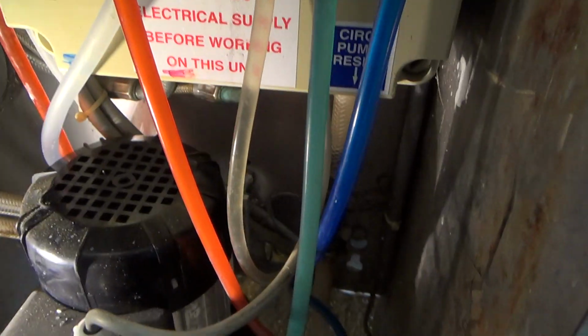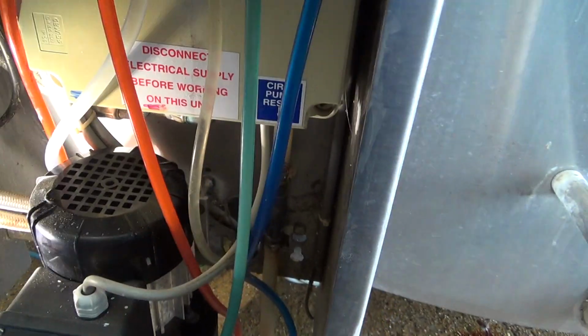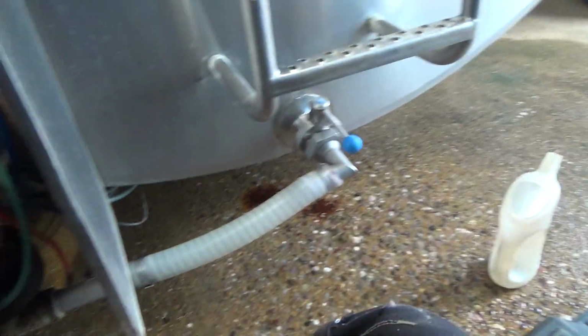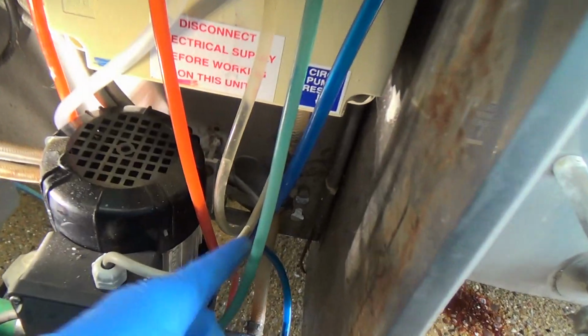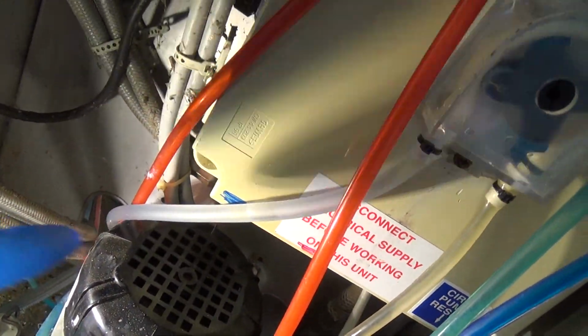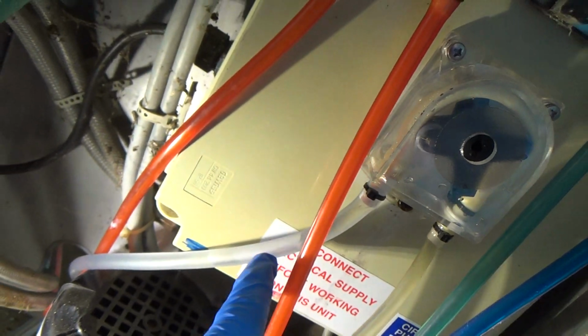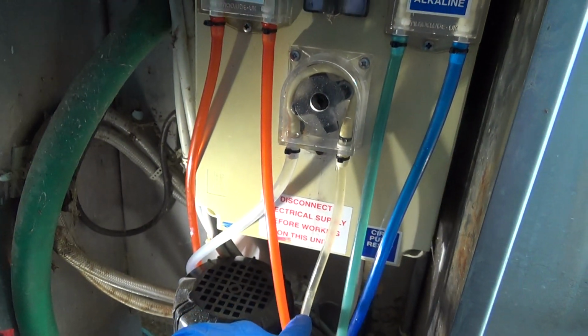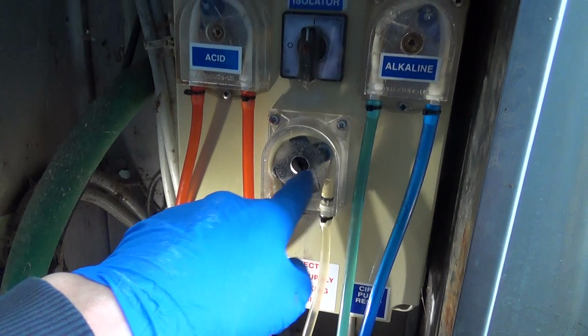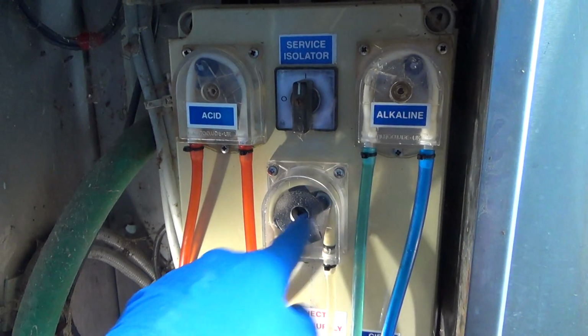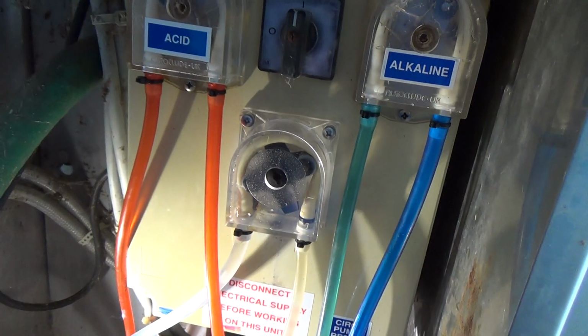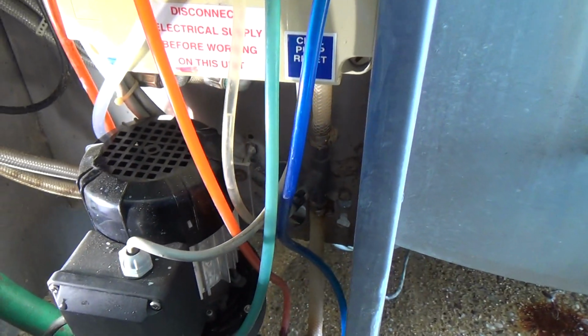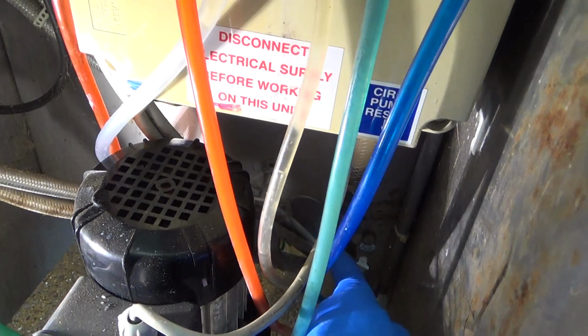I might put another cable tie around that. It just makes me a bit nervous because that's under pump pressure. We haven't got any flow back, so it shouldn't do because the two rollers pinching that tube should stop any flow. Yeah, they just appear to be full of scale crystals.